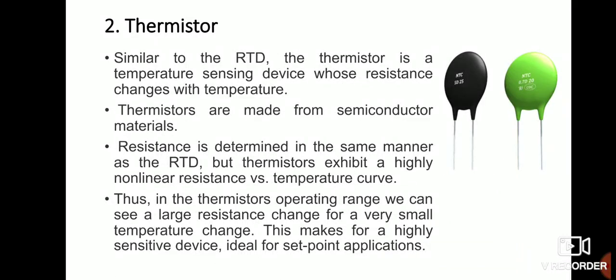The next type is the thermistor, which is similar to the RTD — a temperature sensing device whose resistance changes with temperature. There are two types: PTC (positive temperature coefficient) and NTC (negative temperature coefficient). NTC means as temperature increases, resistance decreases. PTC means as temperature increases, resistance also increases. In most cases, NTC thermistors are used in circuits to sense temperature.